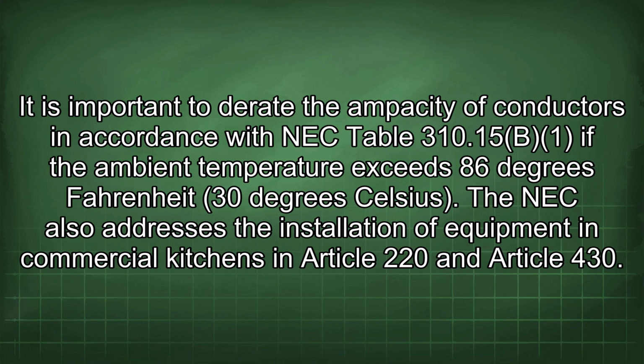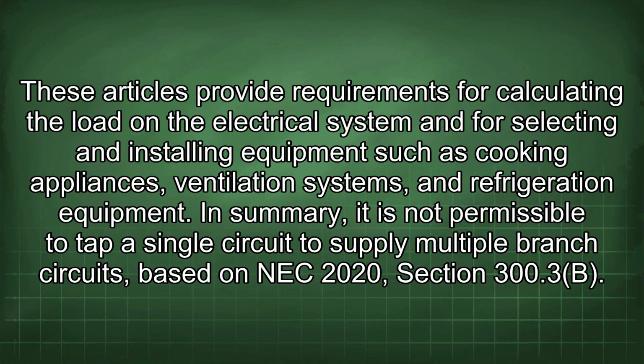The NEC also addresses the installation of equipment in commercial kitchens in Article 220 and Article 430. These articles provide requirements for calculating the load on the electrical system and for selecting and installing equipment such as cooking appliances, ventilation systems, and refrigeration equipment.